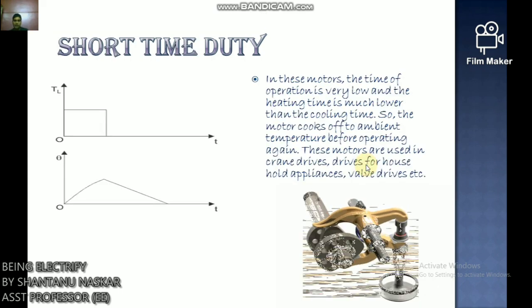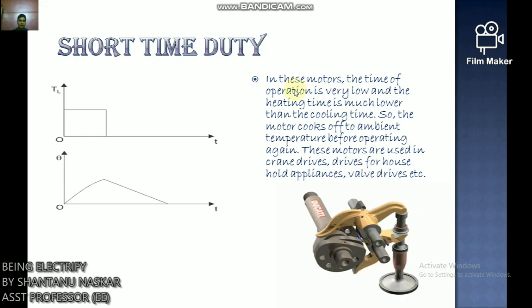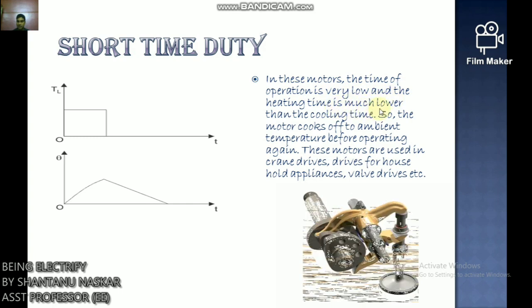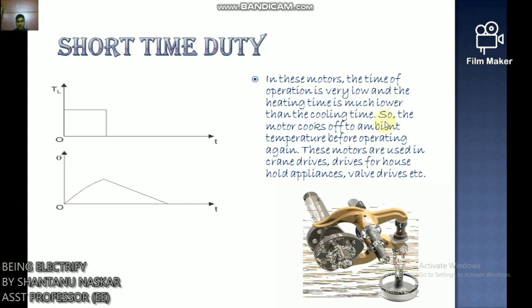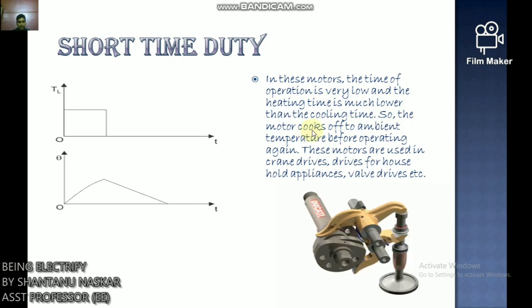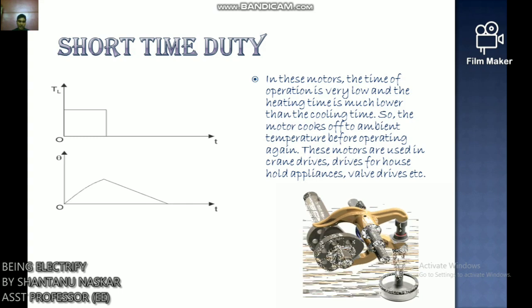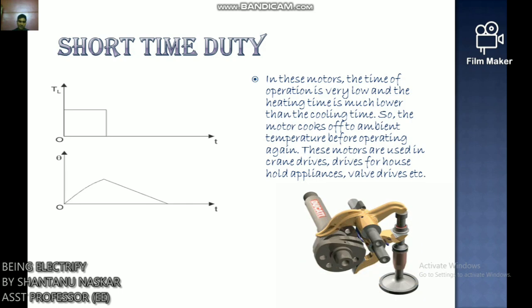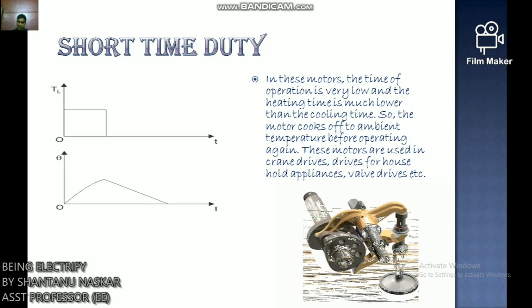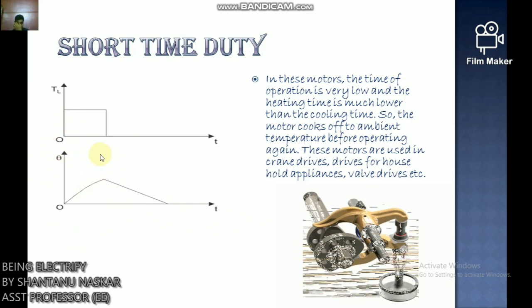Short time duty: In this duty, the time of operation is very low and the heating time is much lower than the cooling time, so the motor cools down to ambient temperature before operating again. These motors are used in crane drives, household appliances, and valve drives.